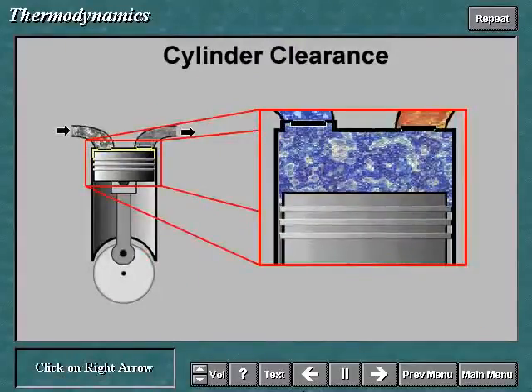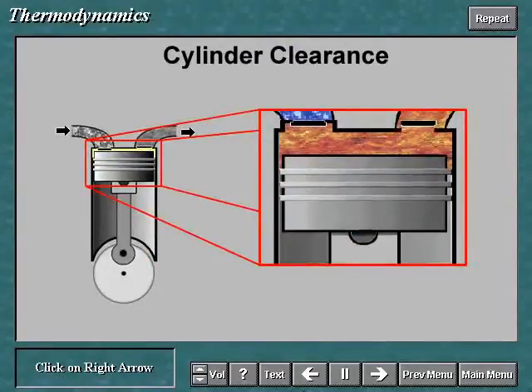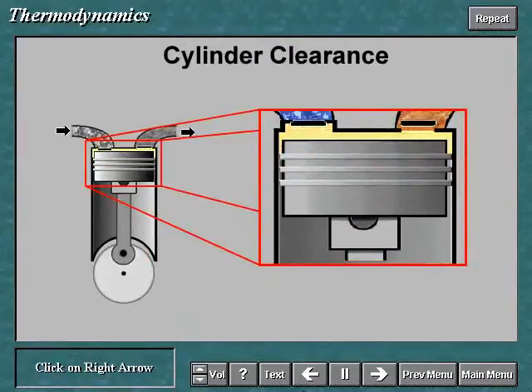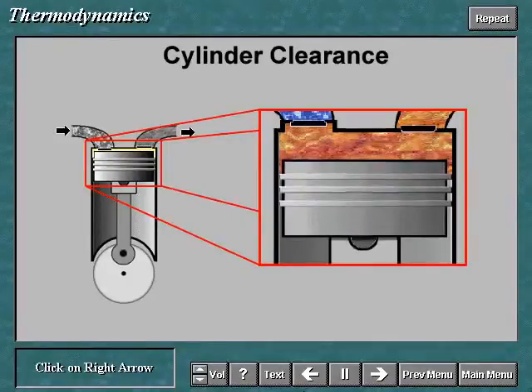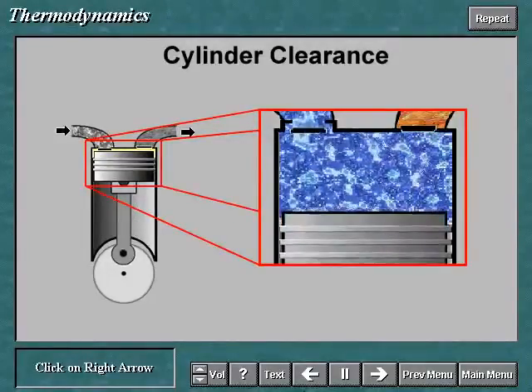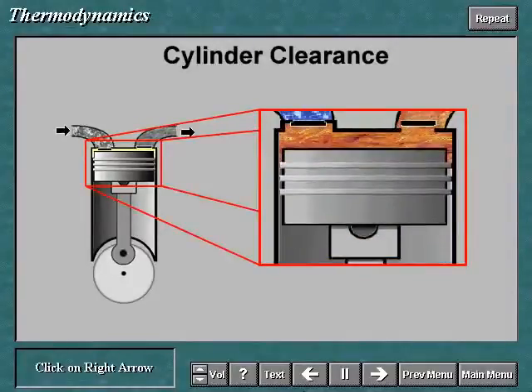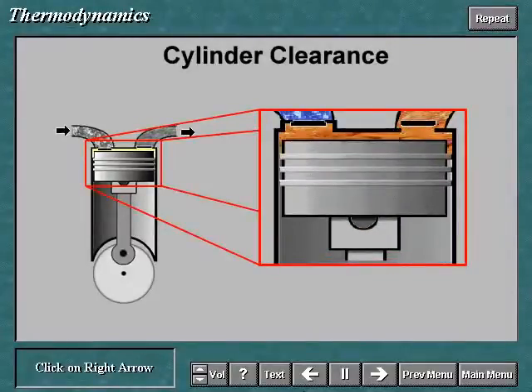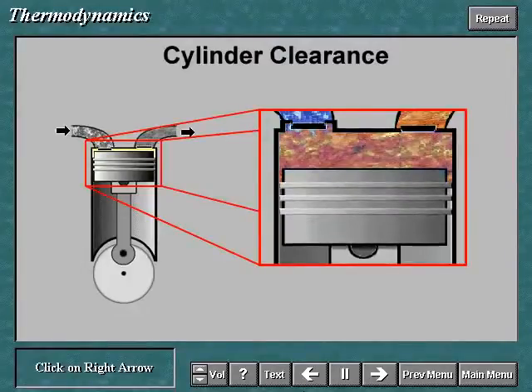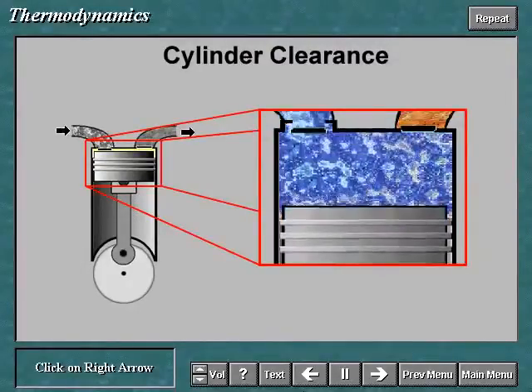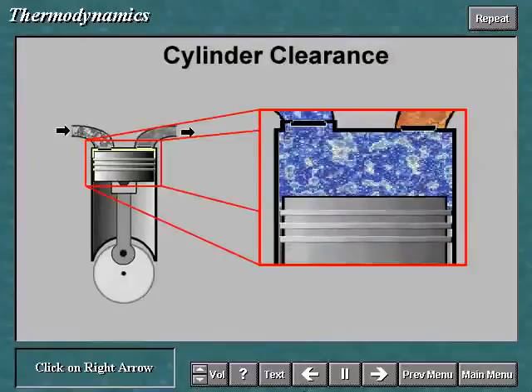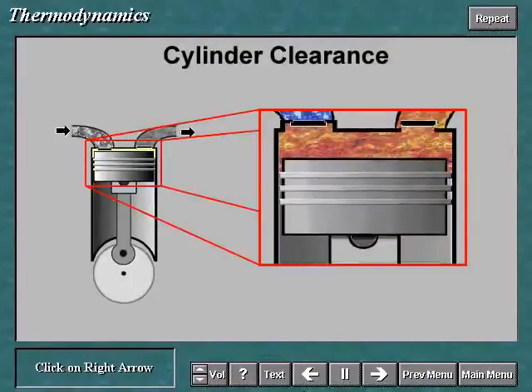Due to cylinder clearance, a certain amount of gas remains trapped within the cylinder at the end of the compression stroke. This gas is under discharge pressure and temperature. The subsequent suction phase can only begin when this remaining gas has re-expanded to pressure P-sub-A. The suction valve will not open until this pressure is reached. This causes a reduction in inlet volume.